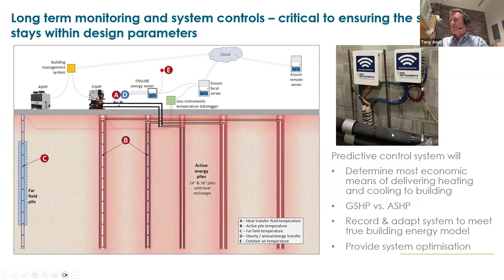This was a screenshot from February this year. We pretty much delivered all of the building's heating here. When we designed this, we thought we'd only deliver about 38% of the building's heating, but we've actually been able to deliver all of it. You can see at the top, the outside air temperature is about 24.67 degrees Fahrenheit, while the ground temperature in February was around 50.